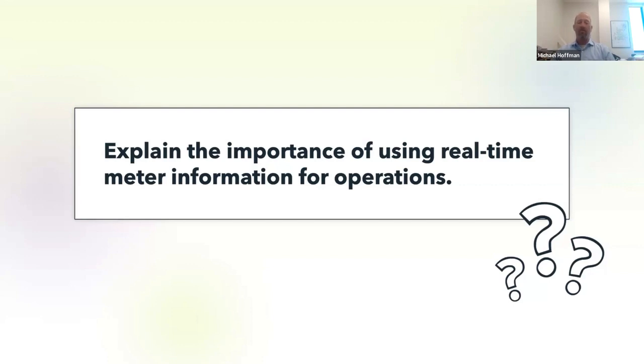So how do I control my peak and maximize the value of that thermal energy storage? I need real-time meter data, because during the summer, when we're on our summer peak period, our central plant stationary engineers are literally watching the real-time demand at our substations from the utility. As we get close to that period where we're going into peak, they start to move us off of chillers and onto our thermal energy storage, because they are managing that peak demand to avoid setting a new peak that would either cost us for the billing period, or even worse, become the new ratchet that follows us for a year.